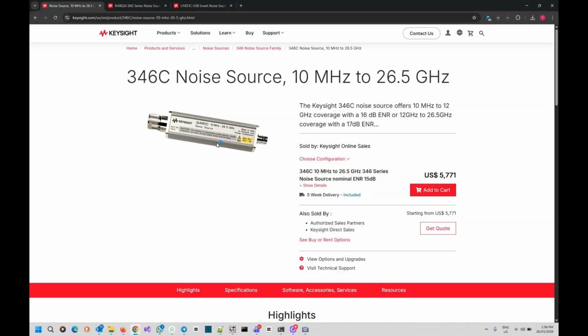This is a manual type noise source where you have to key in the noise ENR table into the spectrum analyzer before you can use it for calibrations or even for measurements. It's using BNC to drive the on and off state. Most spectrum analyzers have this positive 28 volts at the rear of the machine.